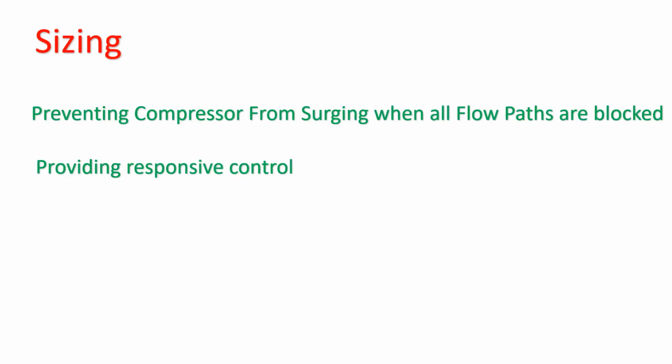There are cases where a large volume of gas needs to be released. In that case, a bilinear trim can be used. So for the 4 to 20 mA signal, the valve will open, and when the compressor trips, another portion of the valve will open, resulting in a larger exhaust of gas, right?